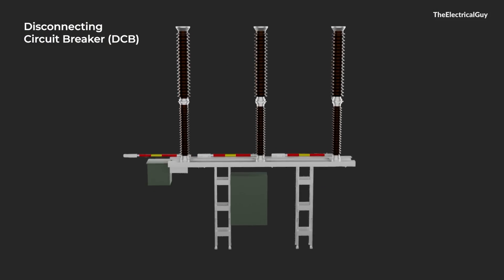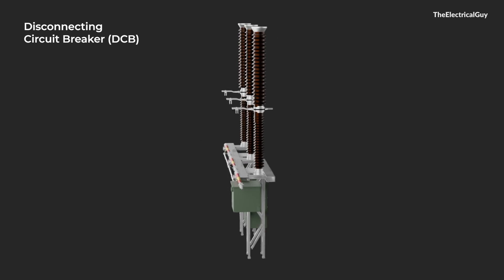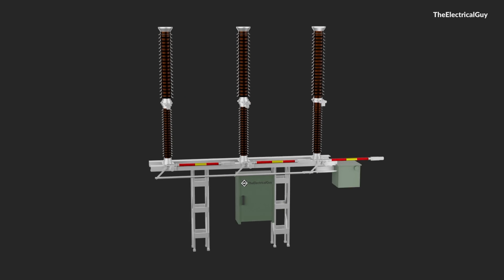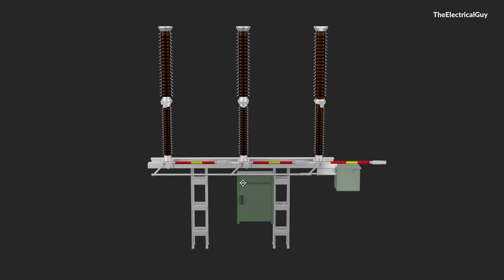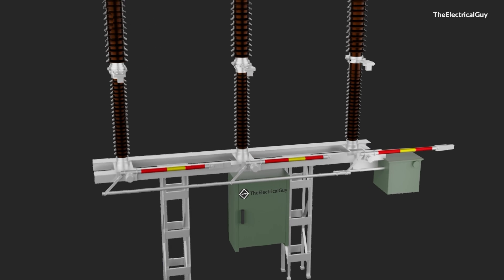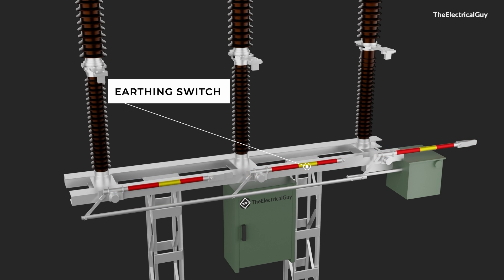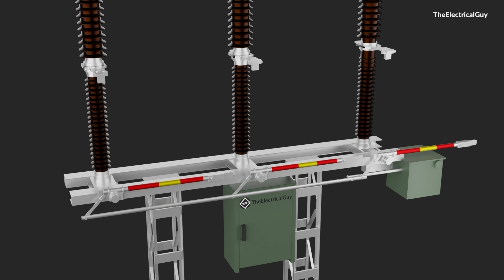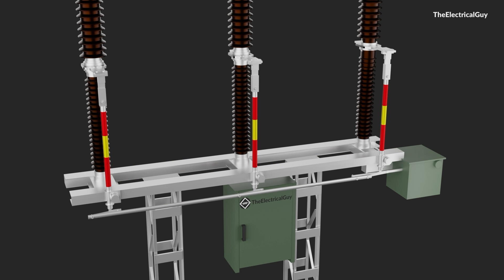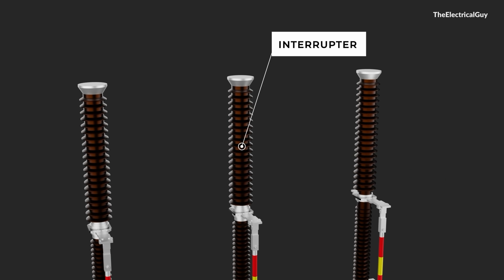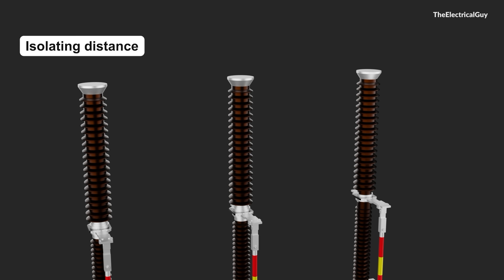Since the disconnecting circuit breaker is a combination of a disconnector and a circuit breaker, it will have all the components of both devices. It looks similar to a regular SF6 circuit breaker, but one notable change is the integrated earthing switch provided with the circuit breaker — needed to earth the trapped charges, a function required by the disconnector. Dedicated earthing switches are provided for each phase. The top part of the breaker consists of the interrupter, just like a regular one, but this interrupter also satisfies the requirement of an isolating distance when in open condition — basically the disconnector function.